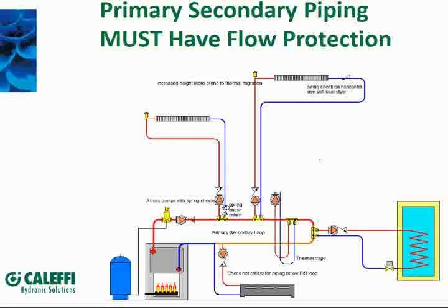So we put a check valve or flow check on the return side also, giving 100% shutoff on both sides. You could put a zone valve in there, but then you'd have to power it. There are different types of check valves — swing checks, spring checks, soft seat checks — and I'll show you the best way to use them.